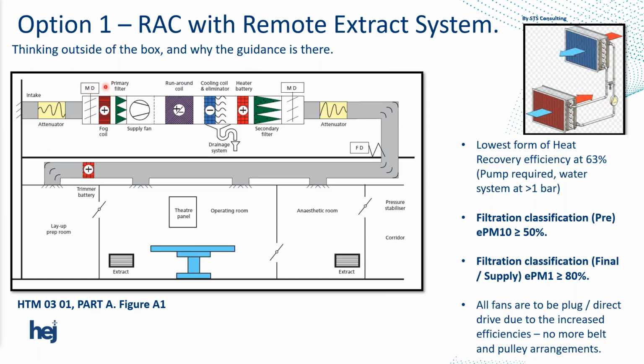There's motorised dampers that sit at each end of the air handling unit, and you'll notice now that this is a fog coil, not a frost coil. So the fog coil's duty or job there is to, firstly, not be finned, because you can see that it's unfiltered, so we want it to be quite an open space. But it's there just to take the air above dew point. So we don't want the outside air getting the primary filter wet, or damp. That's the reason that the fog coil is there. The warmer this fog coil goes, the less efficient the heat recovery section is on any type of air handling unit. So it gives a value of 2K within HTM, and then again, that's the designer's responsibility to look at that.